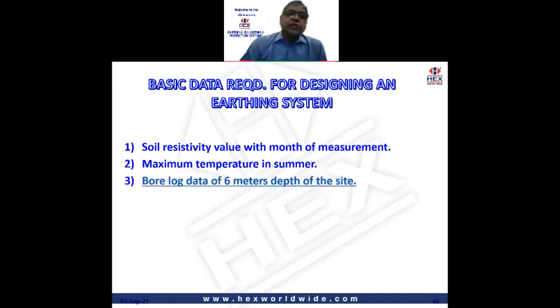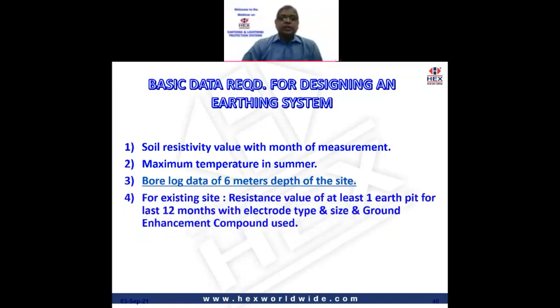Then we also ask for bore log data of 6 meters depth per site. What is bore log data? It is basically the structure of the soil up to 6 meters. We will know at every level up to 6 meters what the soil is made up of and what the resistivity of the soil is, and based on that we can design the best earthing. Now for existing sites, the resistance value of at least one earth electrode for the last 12 months, with the electrode type and size and the ground enhancement compound that has been used.